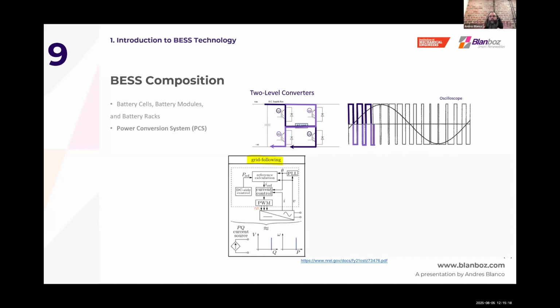The two things I really want you to take away about PCS is that there are two types in terms of functionality. You have your grid-following, which requires the grid to sense the voltage and frequency to operate. If there's a blackout or whatever happens, your PCS is going to shut down.